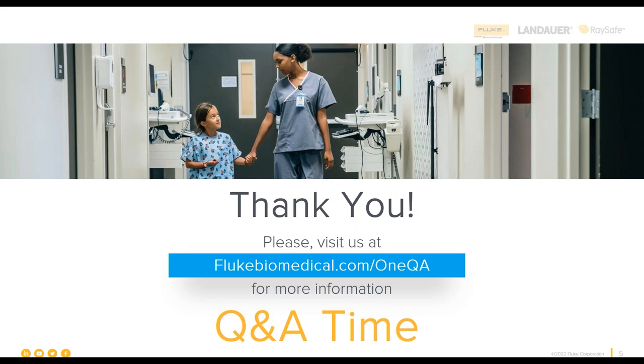You sure can. In this video, you saw that we automated everything. So that automatically pulled the results right from the Fluke device and in. We can also build the questions so that you can hand enter the results. So if maybe today you don't have the Fluke Biomedical ESA, maybe you have a competitor, you can still hand enter those results into it, but still get all the other benefits that OneQA brings, like the pictures and PDFs and all the data into that one central repository.